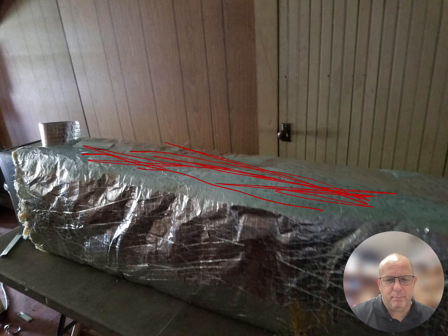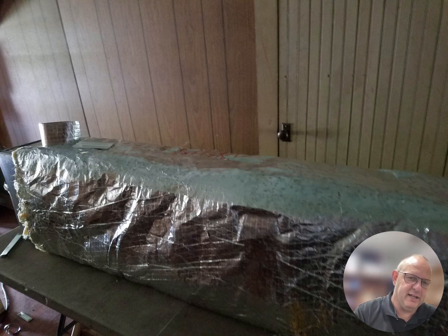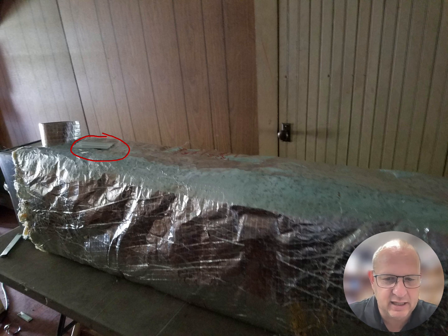I'm going to use a special tool called a blaster or a squeegee, or whatever they call it in the field. That blaster is going to be sitting right there, and all it is is a flat piece of plastic that I'm going to rub over the tape that I've just placed down onto that insulation. That's going to give me a nice tight seal for the foil back insulation that's going to prevent the vapor from entering into the insulation itself and into the ductwork itself. Remember, after you get done stapling it, fold that flap over, and then tape it on there.